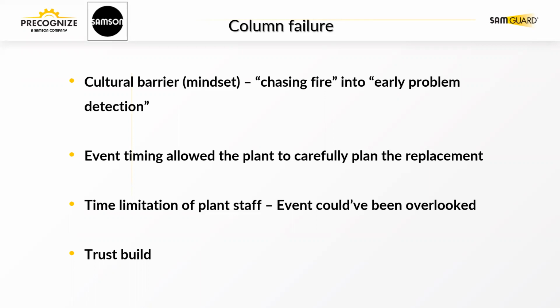And the process team saw this event and they said, I can see that the valve is working again. There is nothing wrong with the OP. The valve is sending in steam continuously, and we don't think it's an issue. So they completely ignored the issue because for them it was normal and they were not concerned about it. But then the valve failed after 2 months.